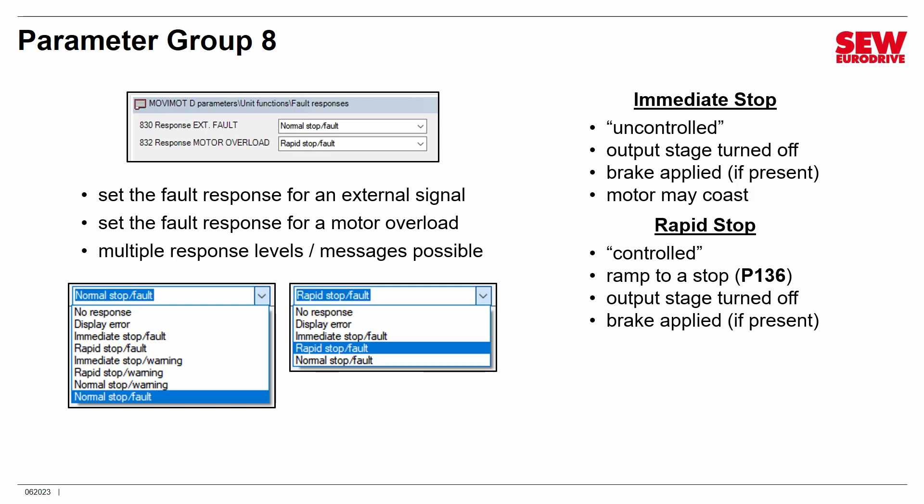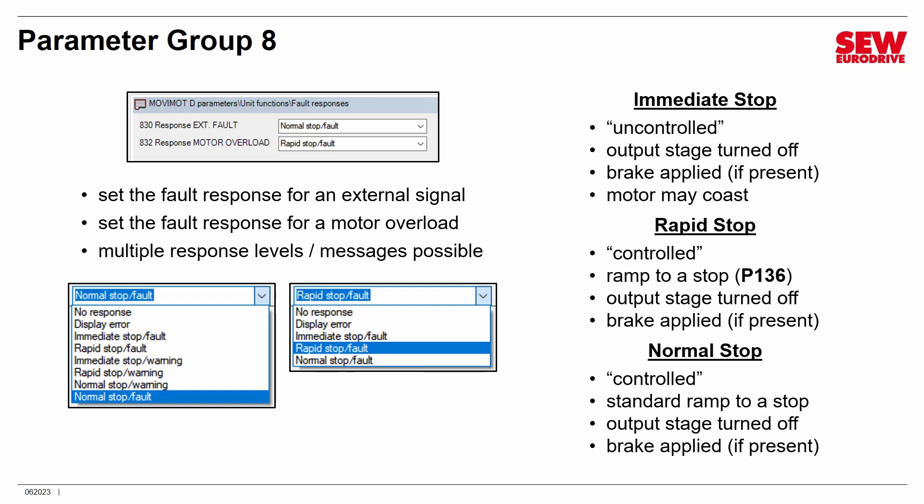Finally, a normal stop is what happens every time you simply disable the motor. In binary mode, if you remove all control signals, you get a normal stop. It uses the standard ramp — either programmed by parameters or the T1 ramp dial — to slow down the motor, then cuts the transistors and applies the brake. You can use any of these three as fault responses. Now it's time for a demonstration — let me show you a few things on the Movimot and demonstrate how some of these parameters work.